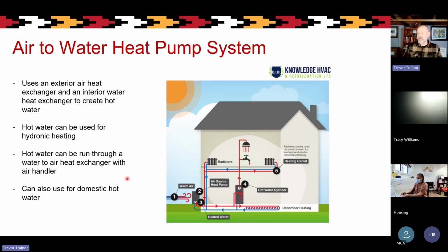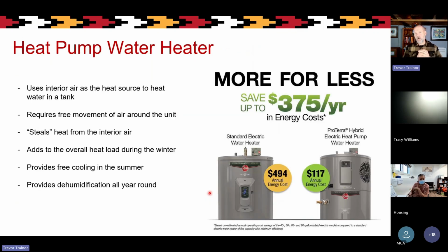So this system can be used for both hot water and heating the home, though it's not as common. These are relatively new in Canada, much more popular in Europe, but starting to become a more realistic option here. There's also a similar air-to-water heat pump system that's just a heat pump water heater. The difference is the compressor sits on top of the hot water tank and grabs heat from the air in the room around it, rather than outdoor air. That adds to the overall heat load in winter, so you have to make up for that with your heating system, but in summer it provides basically free air conditioning to the area it's in, since it's grabbing heat out of the air to warm the water.